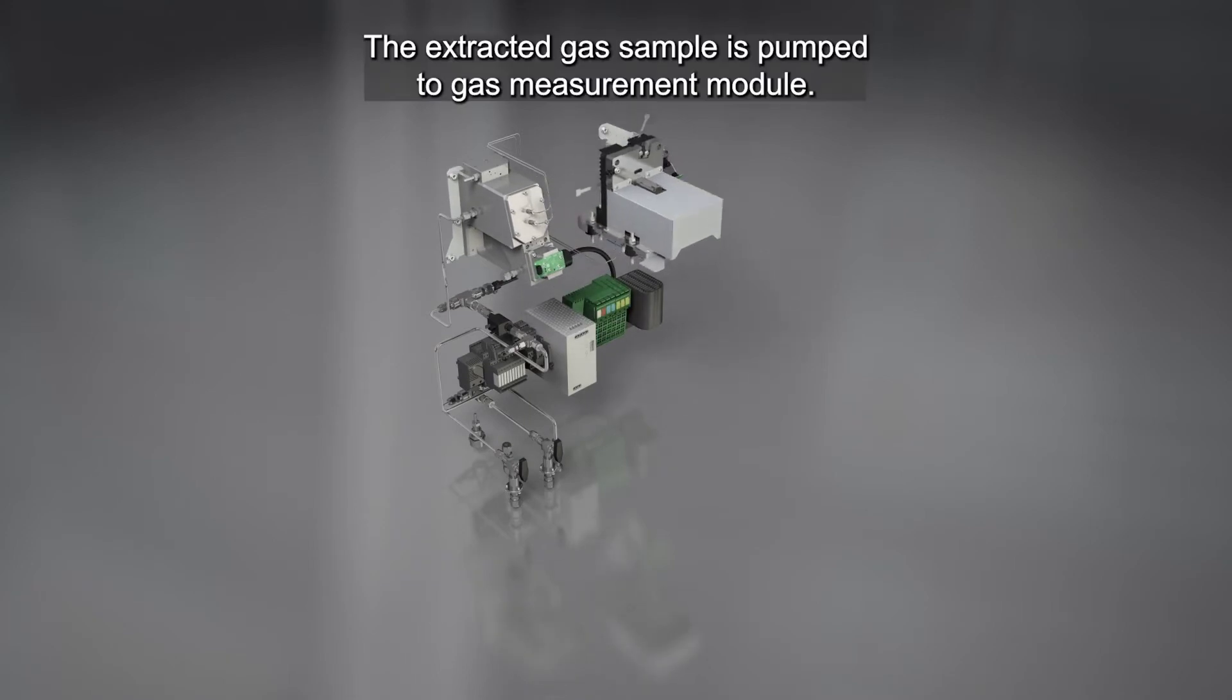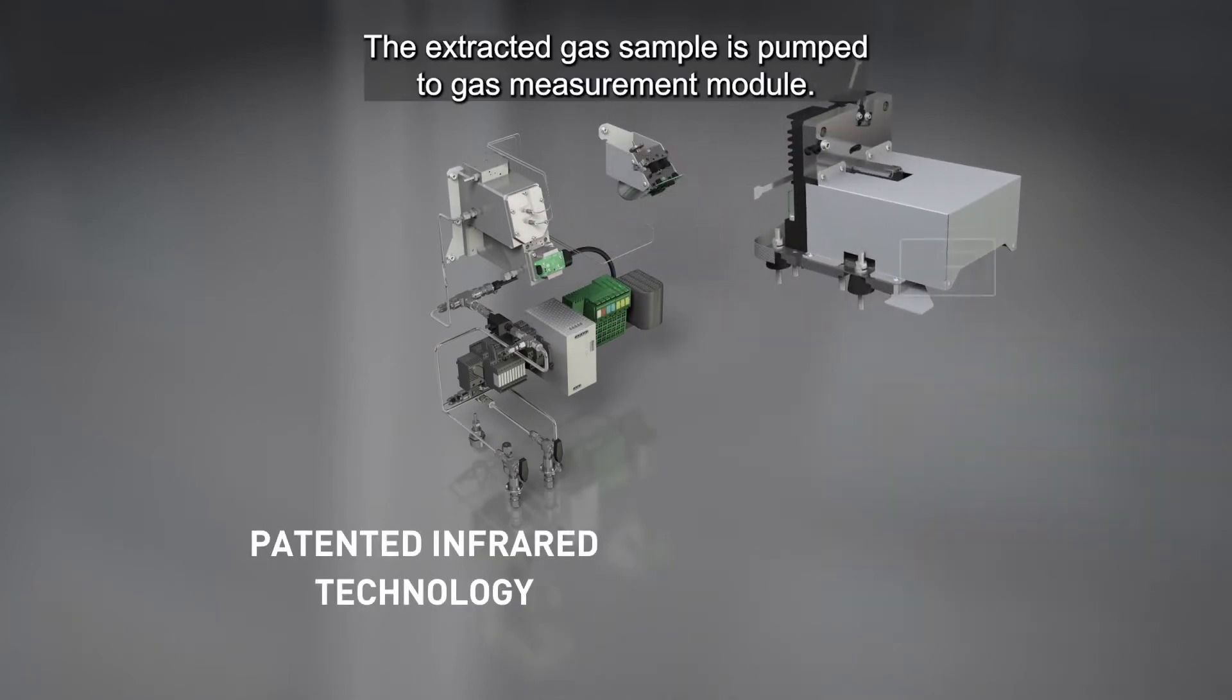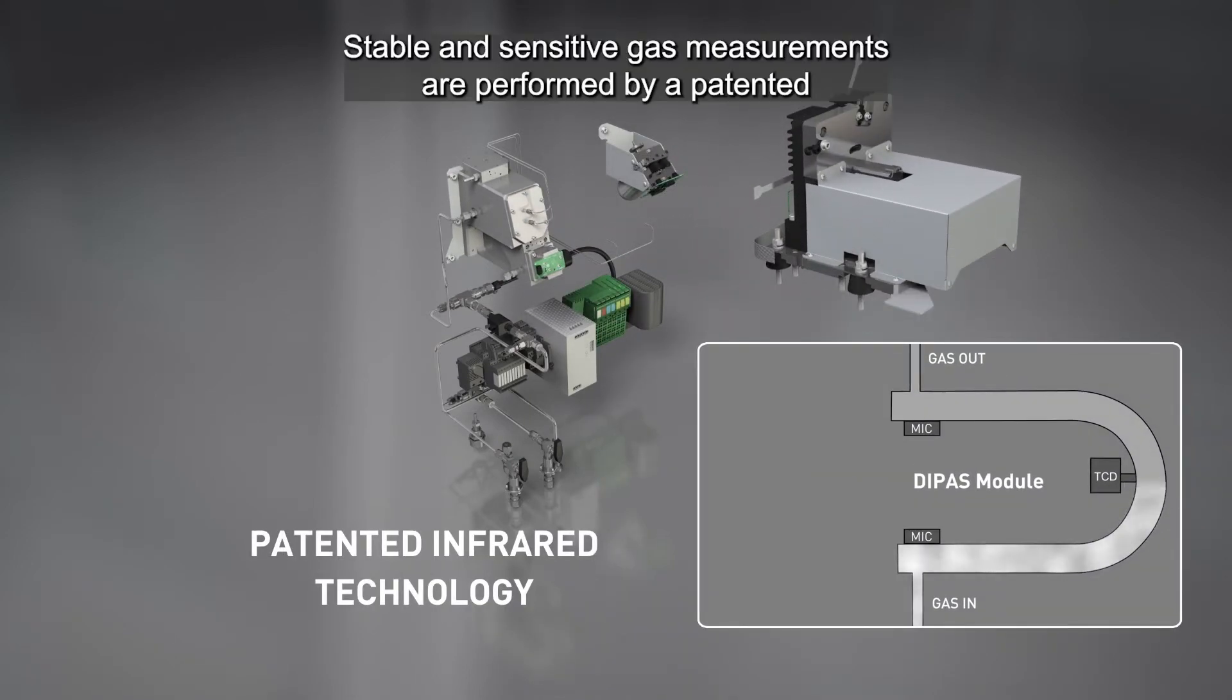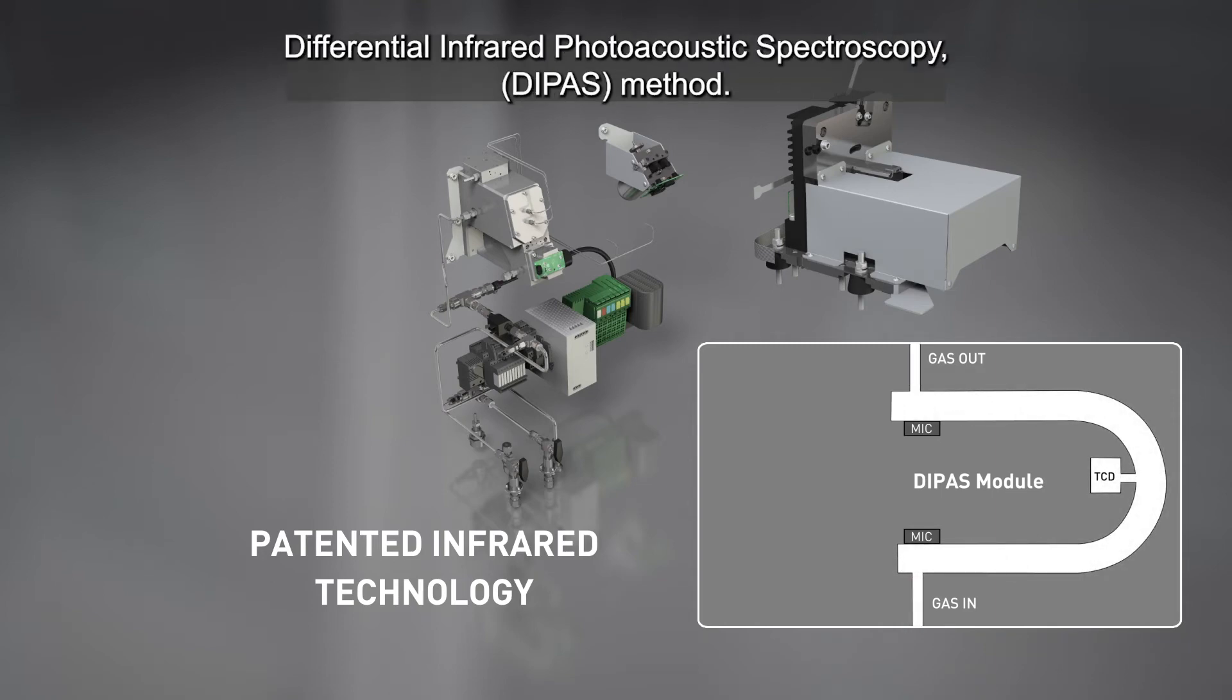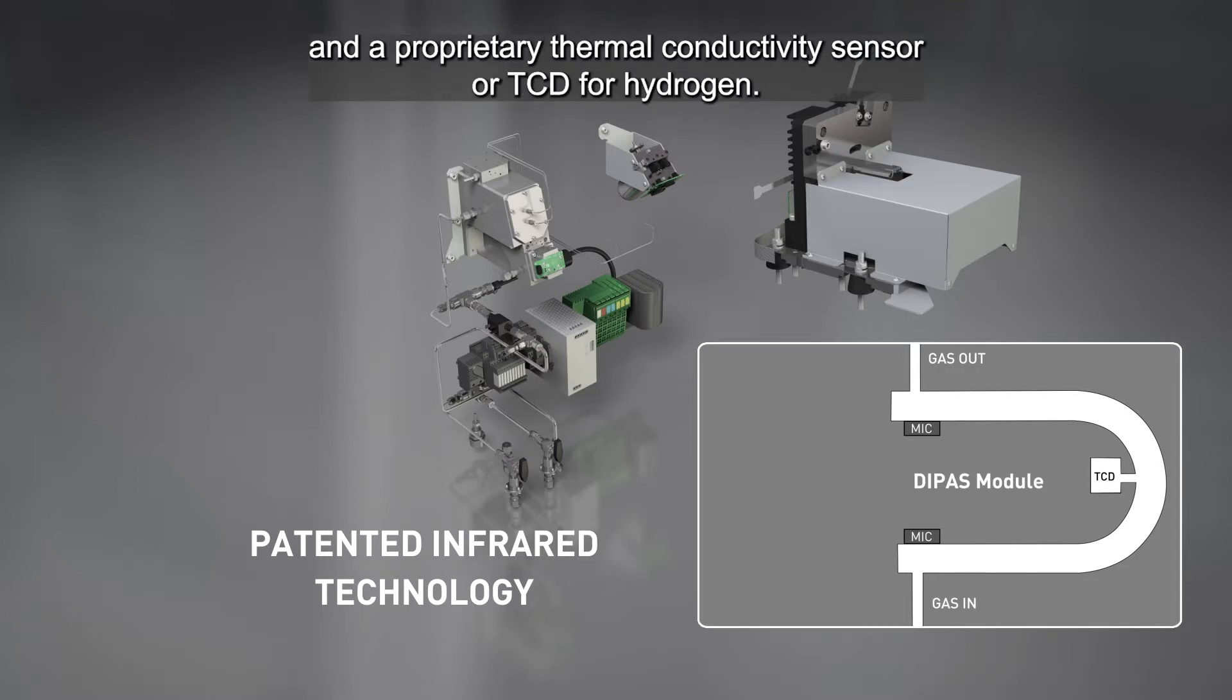The extracted gas sample is pumped to gas measurement module. Stable and sensitive gas measurements are performed by a patented differential infrared photoacoustic spectroscopy, DIPAS method, and a proprietary thermal conductivity sensor or TCD for hydrogen.